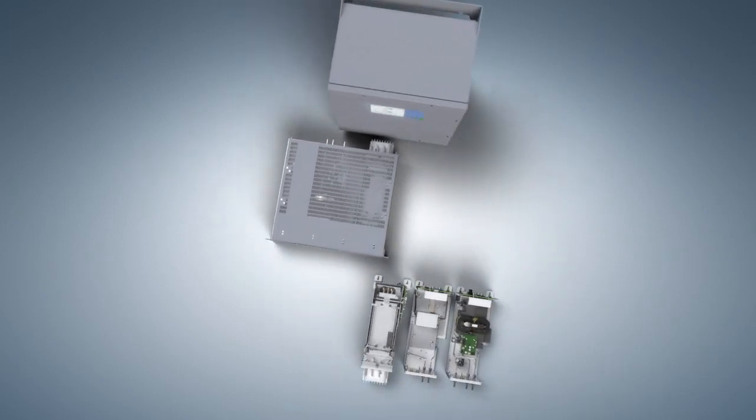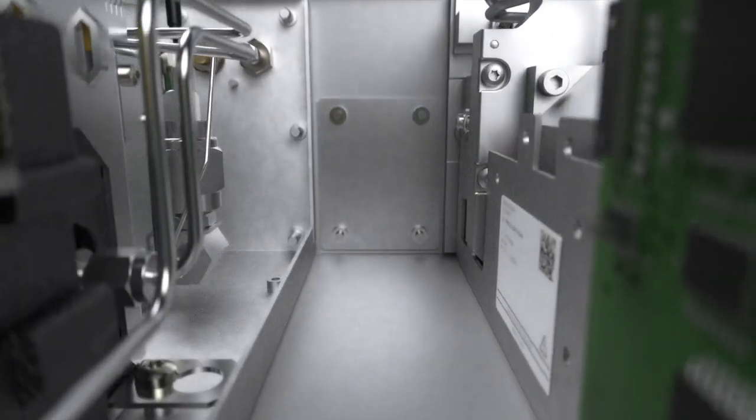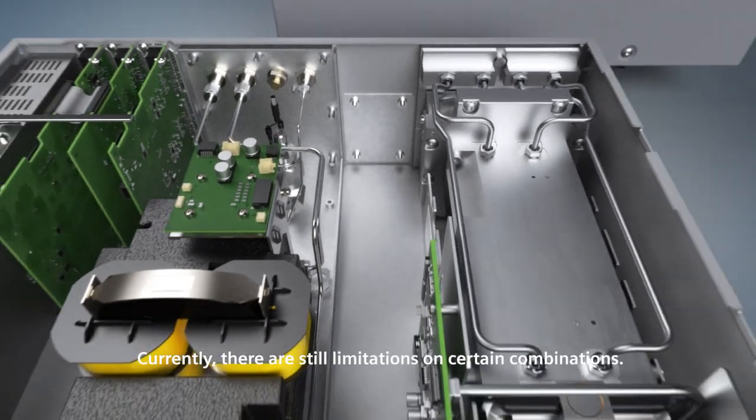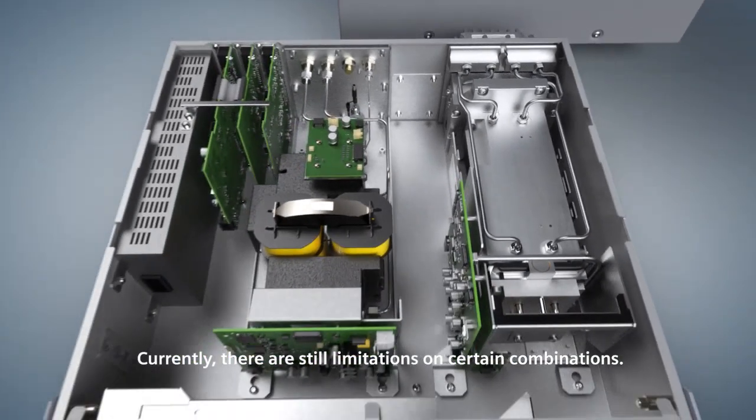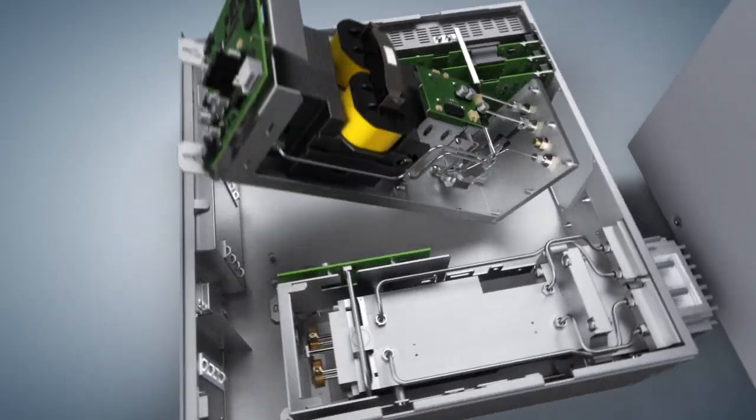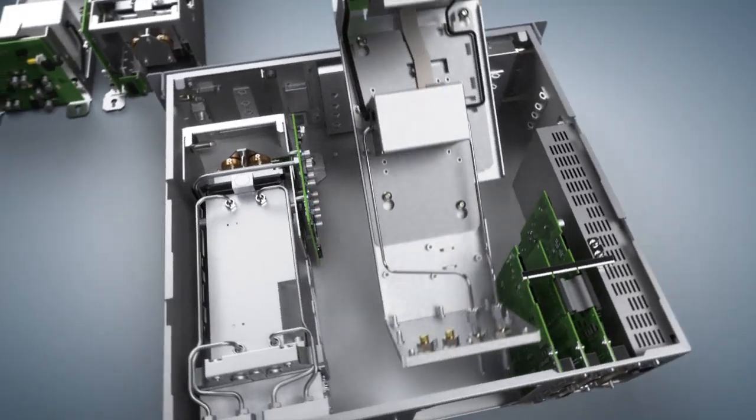Gas analysis has never been easier. The SIPROCESS GA700 is systematic in its modularity. Every housing type now offers space for two analyzer modules. You can combine the Oxymat 7, Ultramat 7, and Calomat 7 exactly as you need, and benefit from fast exchange of modules during retrofitting or conversion.